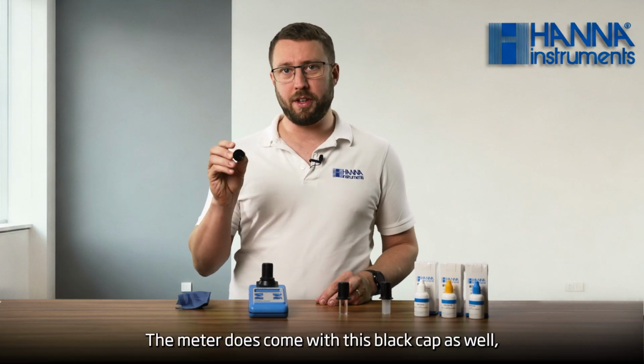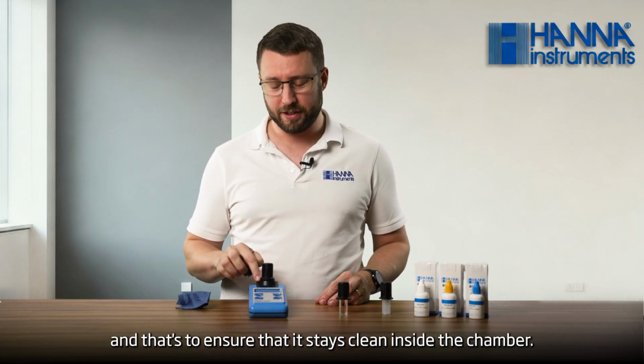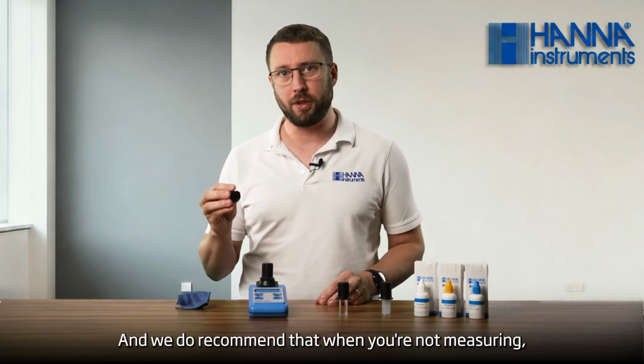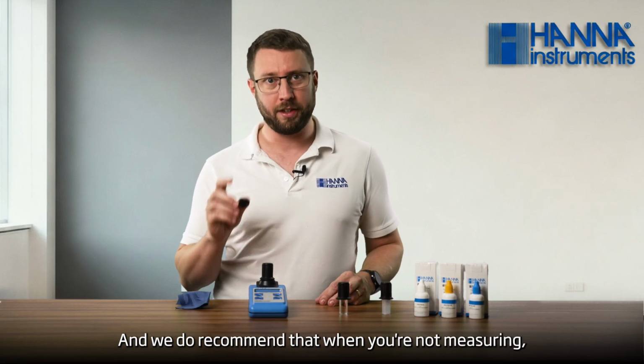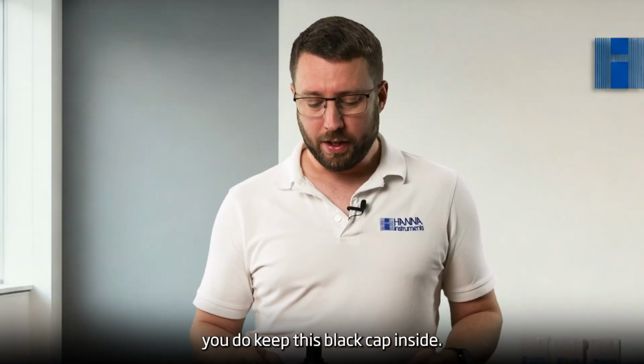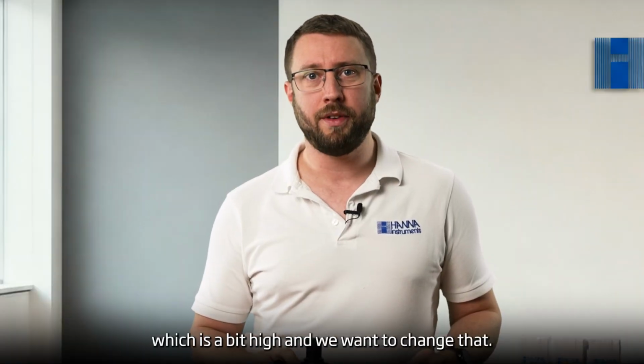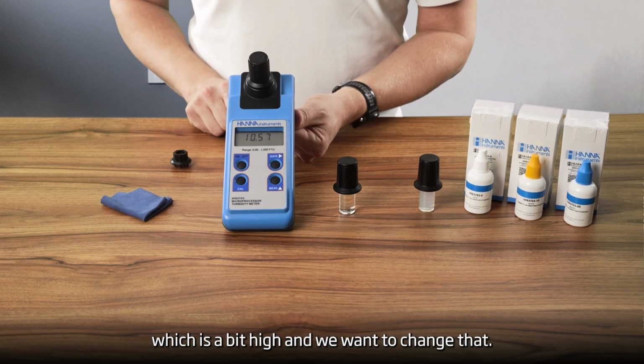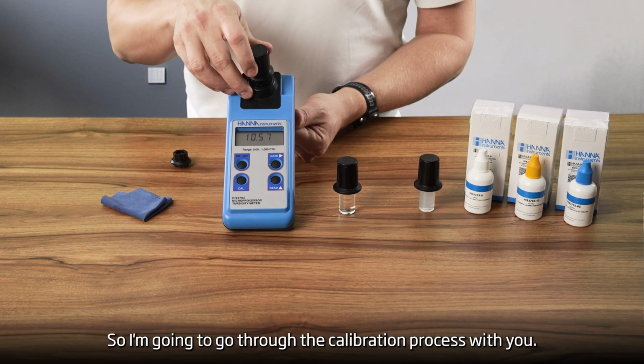The meter does come with this black cap as well, and that's to ensure that it stays clean inside the chamber, and we do recommend that when you're not measuring, you do keep this black cap inside. So that's measuring 10.5, which is a bit high, and we want to change that, so I'm going to go through the calibration process with you.